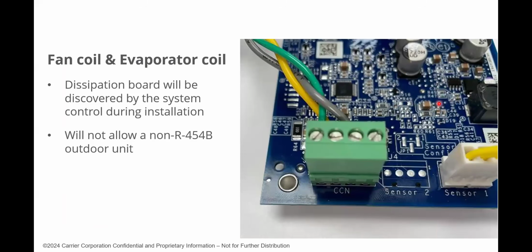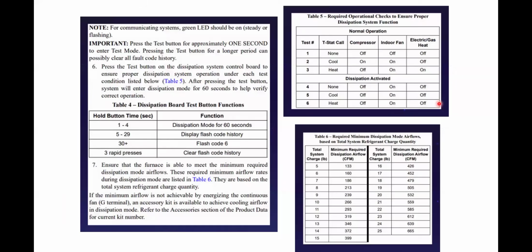We already talked about the communicating ones, so we can skip that. There's one button on that board. If you press that button one time, it'll run a 60-second version of the sequence. So instead of 15 minutes, it'll do a 60-second version, just so the tech can make sure everything's wired correctly.